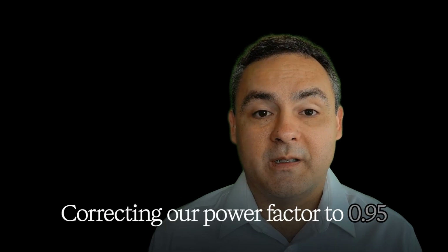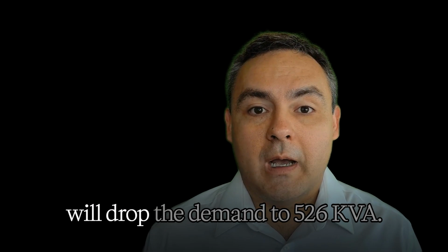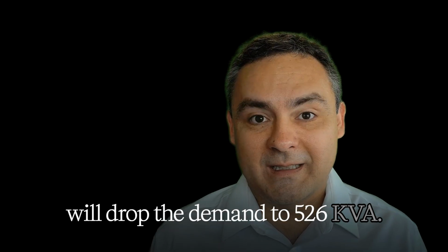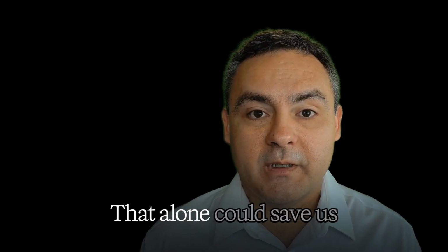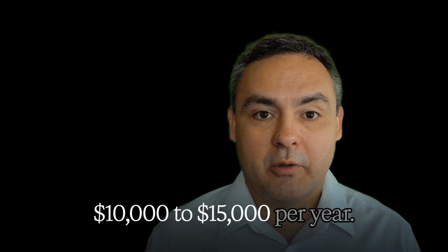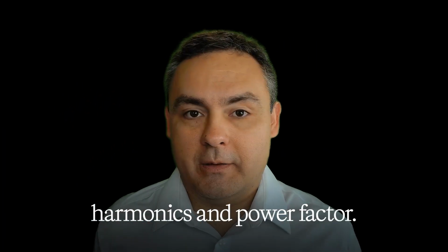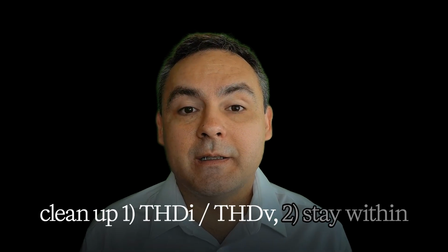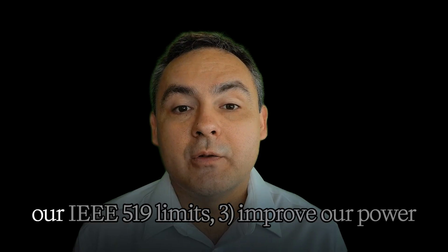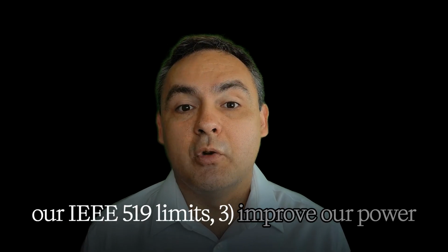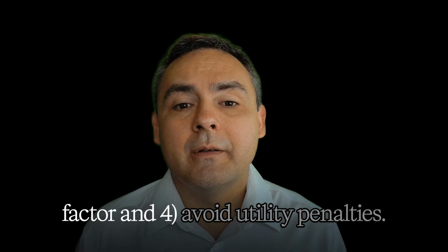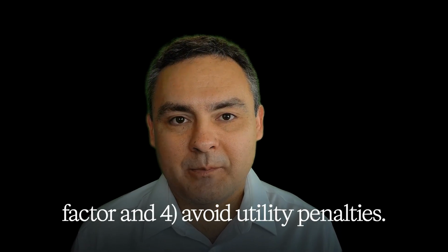Correcting our power factor to 0.95 will drop the demand to 526 kVA. That alone could save us $10,000 to $15,000 per year. Active harmonic filters can correct both harmonics and power factor. With one smart piece of equipment, we can clean up THDI, THDV, stay within our IEEE 519 limits, improve our power factor, and avoid utility penalties.